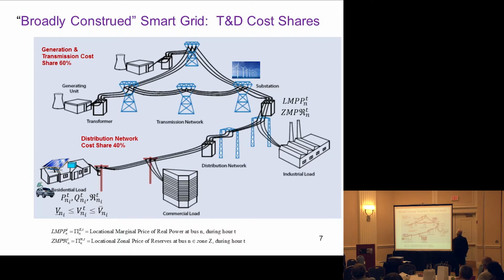At the distribution network, you have congestion that reveals itself in different ways. We don't have capacity constraints that we enforce like we do in the transmission system. In the transmission system, if we try to overload a line with a thermal capacity constraint, if we don't make sure not to overload it, the line is going to sag and then disconnect and create disruptions that may be very costly. So here we try to enforce capacity constraints.